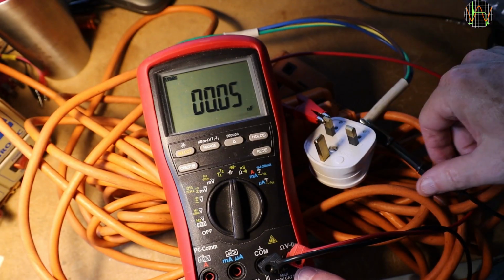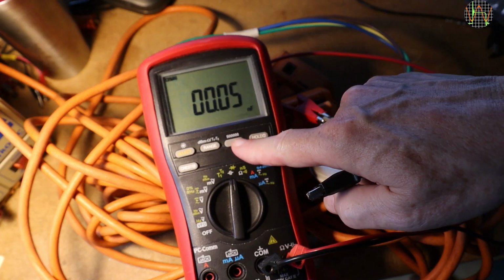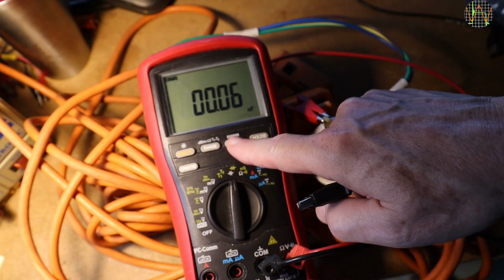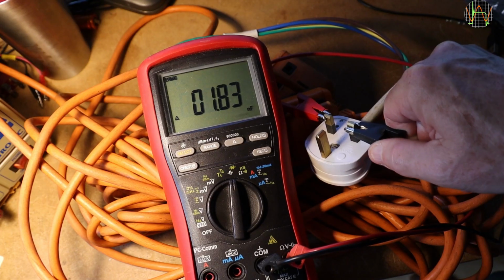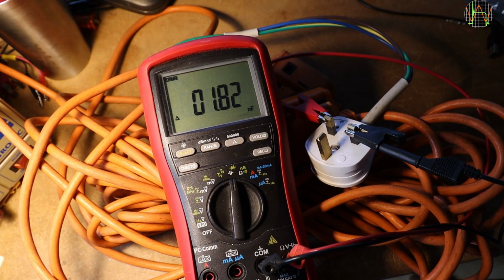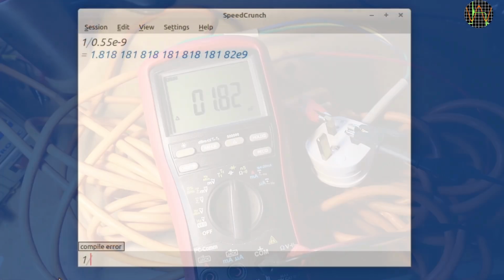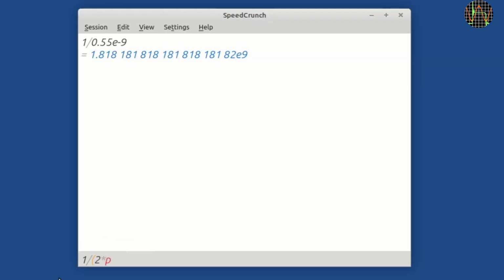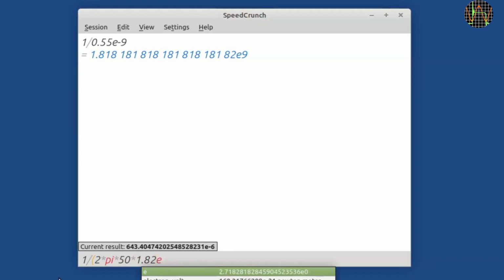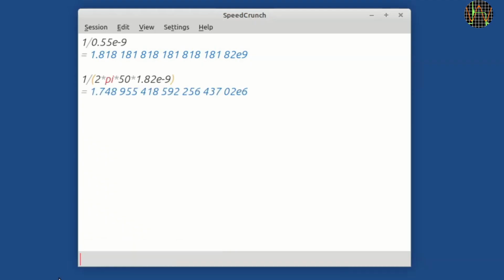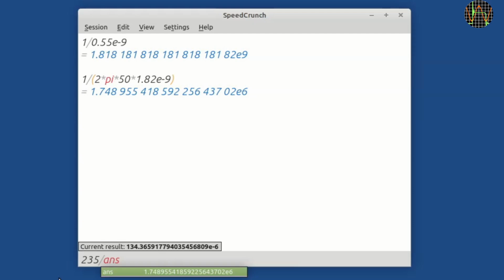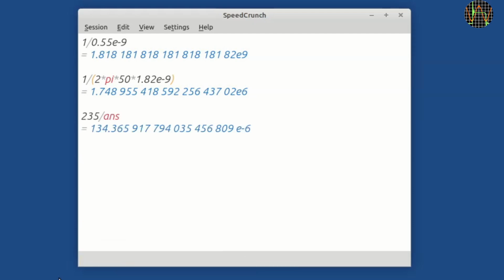But here we are using AC, not DC. Let's see what capacitance the cable has. Zeroing the residual capacitance first. We get 1.82 nanofarad. Now, to convert that into reactance, we need to take the reciprocal of 2 times pi times the frequency, 50 Hz in this case, times the capacitance. And it gives us about 1.75 megohm. And dividing the mains voltage of say 235 volts by this gives a current of 0.134 milliamps, which is reasonably close to the leakage current we measured earlier.